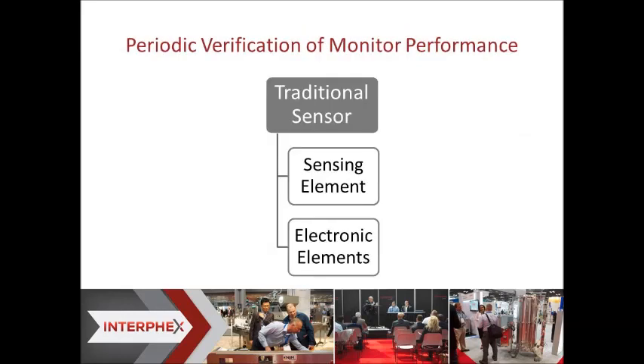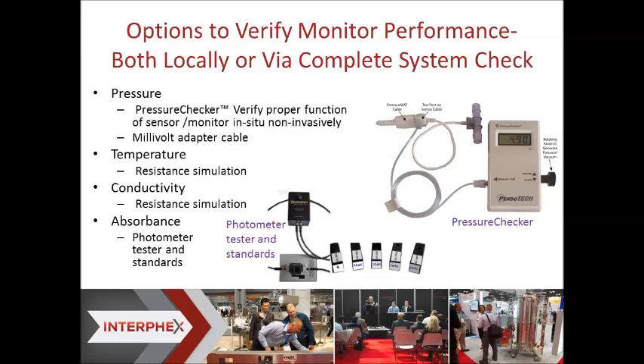So in terms of the metrology groups I mentioned, a lot of people want to implement the technology, then it kind of lands in the hands of the metrology group that has to figure out what to do. So one thing that's very wise is to perform some sort of verification of the monitor performance. So this is really taking the sensor out of the loop. Because remember we mentioned in the beginning with the single-use sensor, it's really a traditional sensor broken into two pieces. One is the sensing element, which is in the sensors we just saw, and the other is the electronic elements. So periodically, people may want to just verify the accuracy of electronic elements. We have a range of tools and advice that we can give to people that do want to measure the performance of their monitor only.